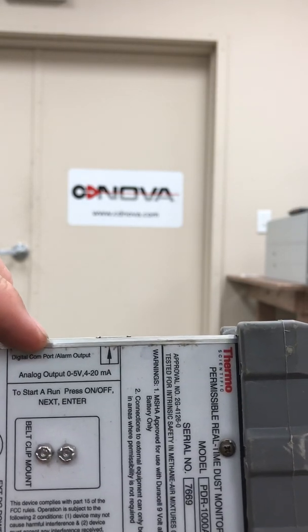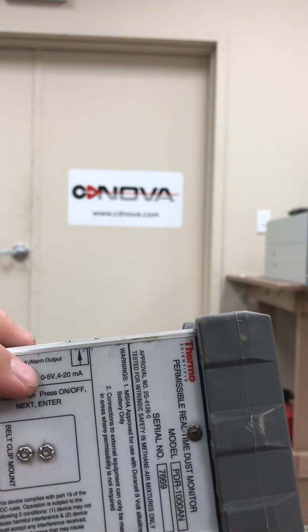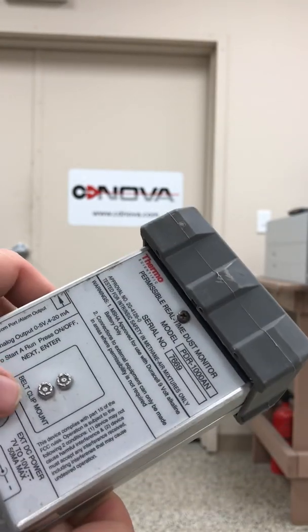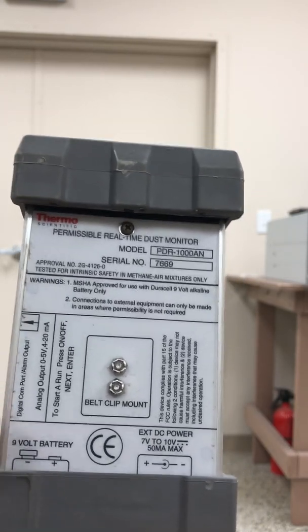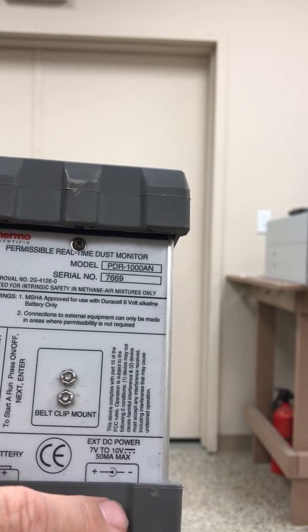That way I can show you the battery pack on the bottom. If you look at the back of the unit, it actually has some labeling to explain what some of these ports are. This is a digital COM port alarm output with an arrow pointing up. So if I turn this unit, you can see the port — it's a phone jack. And that's the analog output: 0 to 5 volts, 4 to 20 milliamp output off this port right here. There's a belt clip mount with two nuts — you can have a belt clip mount attached here so you can walk around with this unit. It explains where the 9 volt battery compartment is, just underneath this lip here. And there's an external DC power 7 volt power adapter you can plug in underneath here as well.